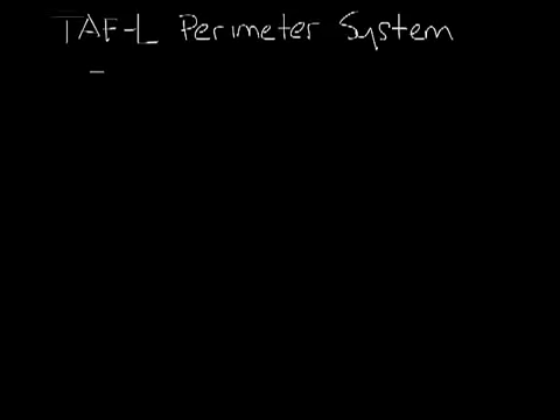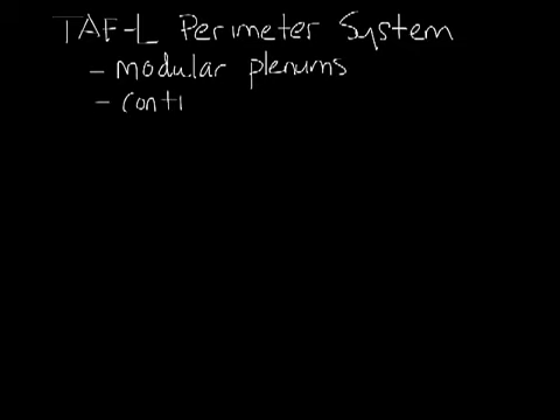The TAF-L system has modular heating and cooling plenums that use no additional fans and have a specially designed linear bar grill to keep the throws short. The cooling plenum, the TAF-LV, uses the pressurized air under the raised floor to supply the perimeter with cooling.